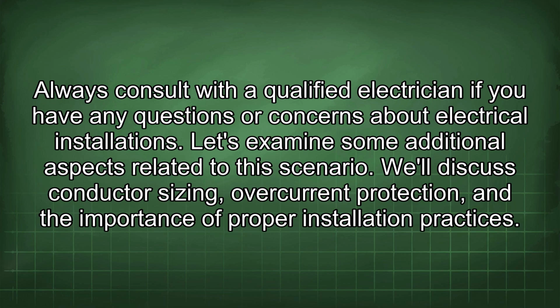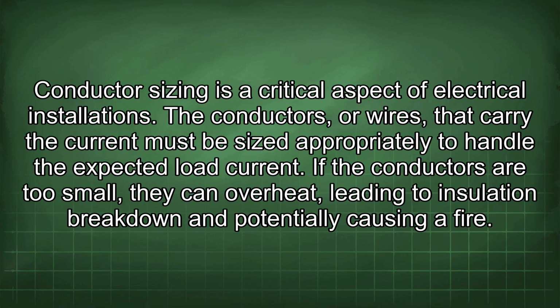Let's examine some additional aspects related to this scenario. We'll discuss conductor sizing, overcurrent protection, and the importance of proper installation practices. Conductor sizing is a critical aspect of electrical installations. The conductors, or wires, that carry the current must be sized appropriately to handle the expected load current. If the conductors are too small, they can overheat, leading to insulation breakdown and potentially causing a fire.